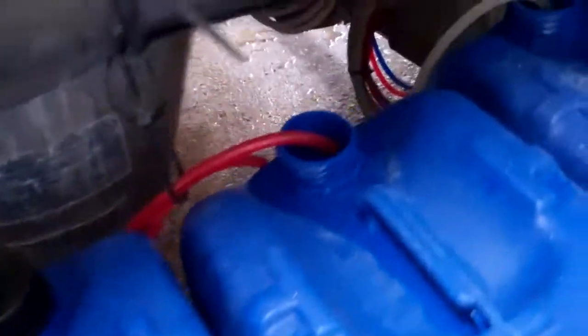The other thing you get is if the leak's behind one of the legs, you get oil staining on the threads. But they look okay. That one looks a bit oily, but I think most of these came out earlier.